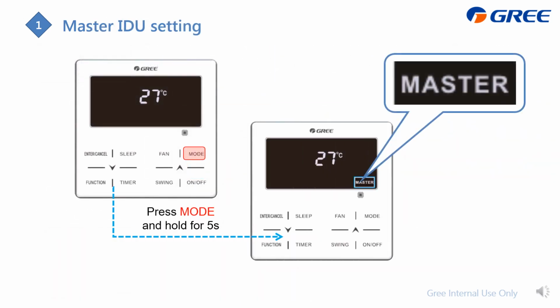Master indoor unit setting. To set it, during the off mode, just like this, long press this mode button for 5 seconds. Then this connected wire controller or connected indoor unit will become the master, and here we display this master icon.